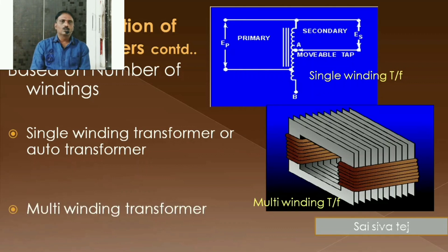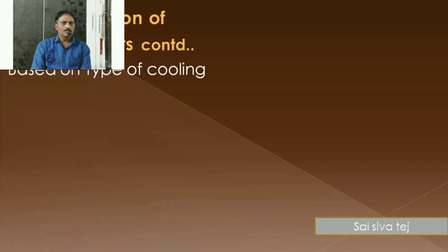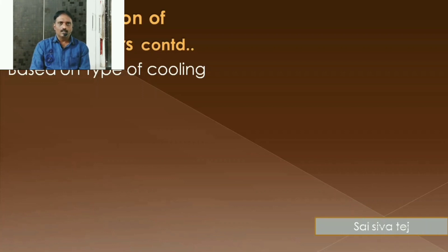Based upon the type of cooling, the cooling mechanism is essential for transformers. The reason why we require cooling is that transformers are going to be subjected to different kinds of losses, like core losses and copper losses. Sometimes they are going to be operated at very large loading conditions — nearly 150% of the rated load during summer season when all the air conditioners are switched on. Whenever it is heavily loaded, the transformer experiences different types of losses and gets heated up. If no cooling mechanism is provided, the temperature is going to rise abnormally and there is a possibility that the transformer may get damaged.